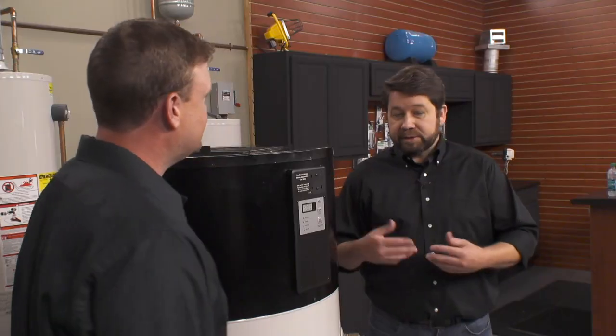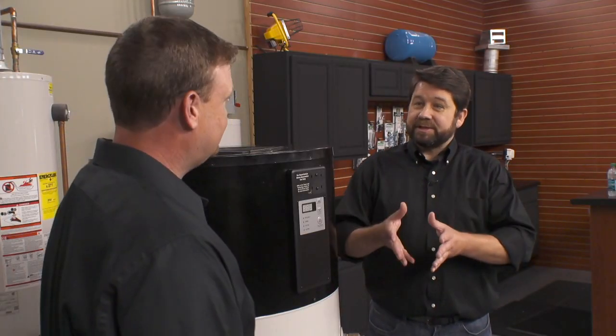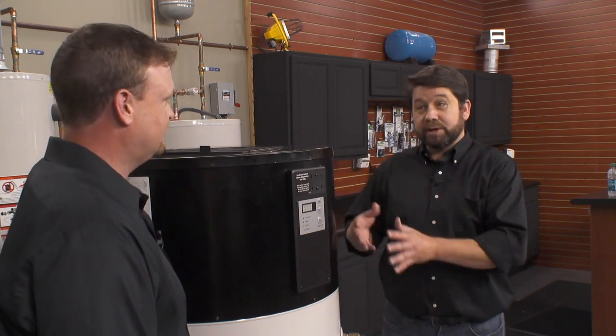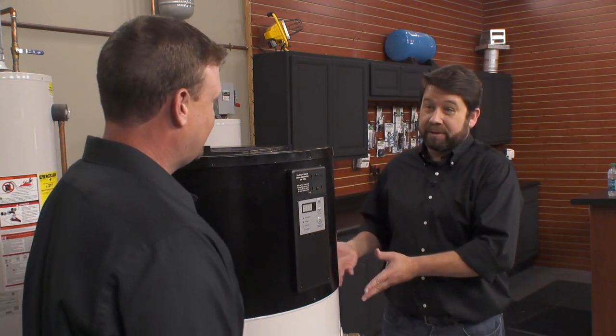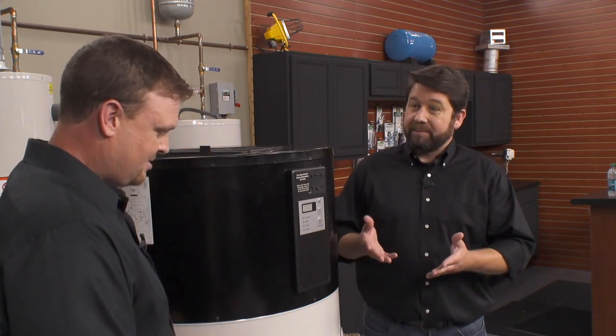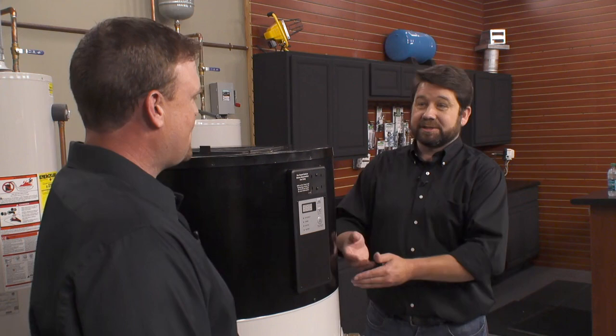EF rating takes into account a few different things like standby heat loss and thermal efficiency, and wraps it into one number. The higher the number, the more efficient the water heater is. In layman's terms, it's a percentage of how much of the energy we put into the product is turned into usable energy, in this case hot water. A normal electric water heater might be 0.9 or 0.95 efficient, so 5% of that energy is lost out from standby loss or through insulation.